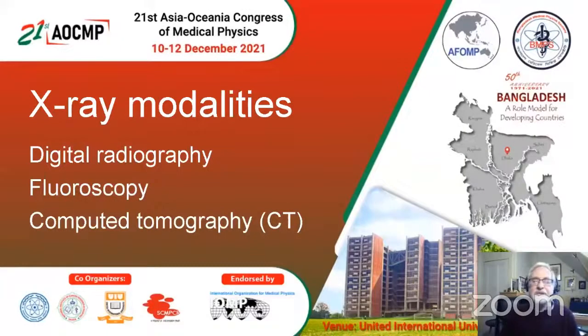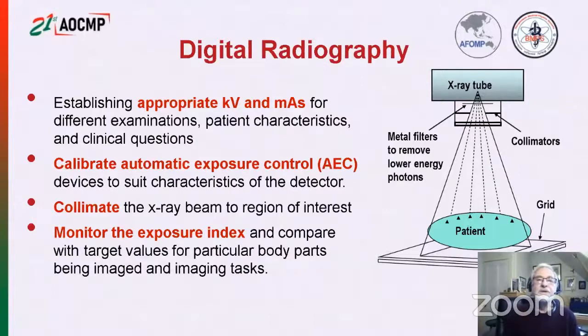So I want now to look briefly at some of the X-ray imaging modalities. For digital radiography, we need to establish the exposure factors, kV and mAs, but an important thing is to calibrate the automatic exposure control, because that has quite a significant effect on the exposure for radiography systems. Radiographers need to collimate the X-ray beam to the region of interest. Another thing is to monitor the exposure index on the digital system, because this gives an indication of the exposure level, and we can set target levels for particular body parts being imaged. That can help us in picking up any exposure creep.